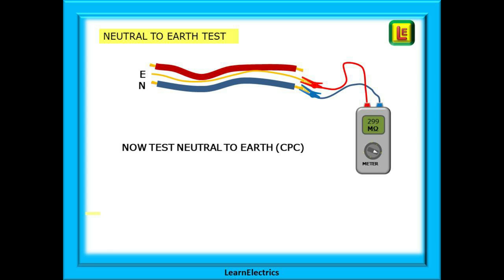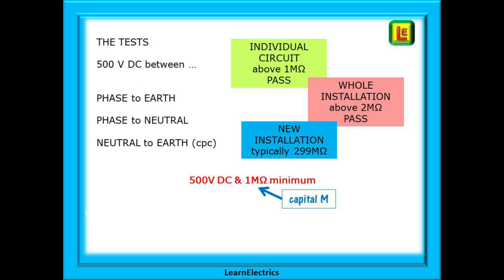More about the tests soon. So just a quick recap: we will test at 500 volts DC, testing from phase to earth, from phase to neutral, and from neutral to earth. For a pass, an individual circuit should measure above one megaohm of resistance for any of the tests. And the whole installation should have a combined parallel resistance above two megaohms. A typical new installation would give the test meter maximum — 199 or 299 megaohms for example, a lot higher with some modern meters.